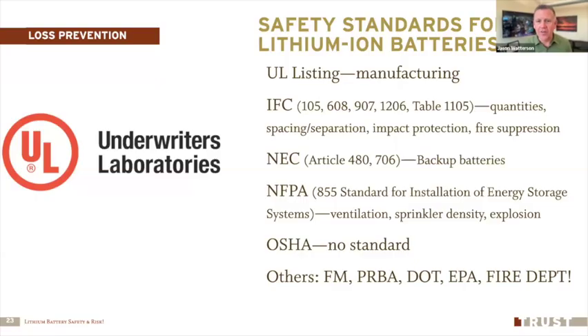Years ago, when I started the Trust, I said, we have these servers, we need some protection for those. So I recommended it, and we went through a capital process to put in this system to protect the servers in the event of a fire, without having our sprinklers go on and ruin the servers anyway. Well, after about 15 years, that system triggered, due to a failure in this UPS system.